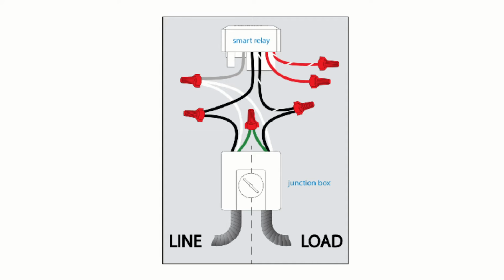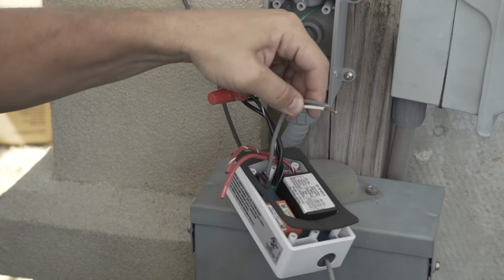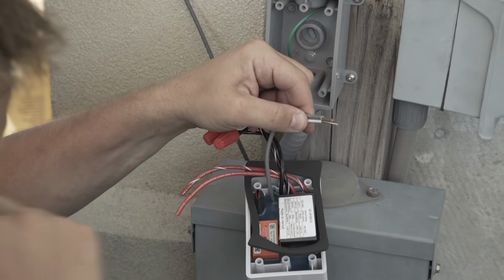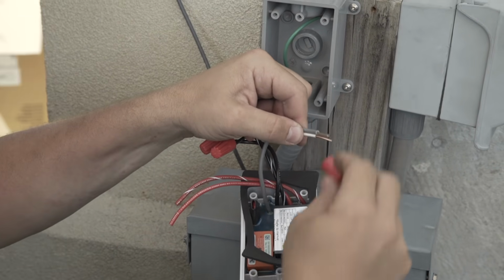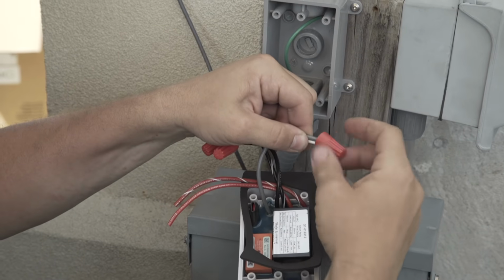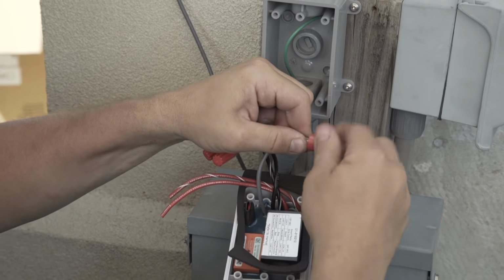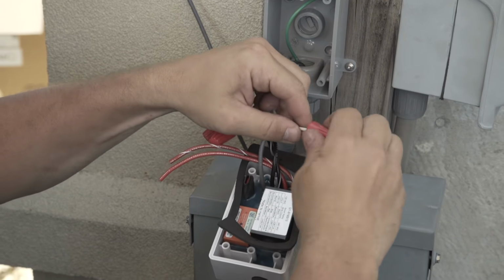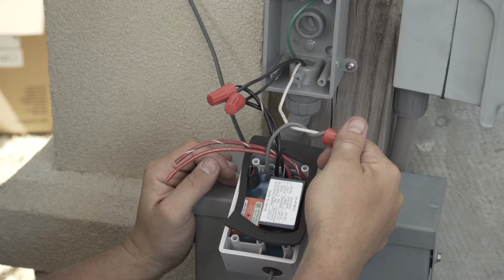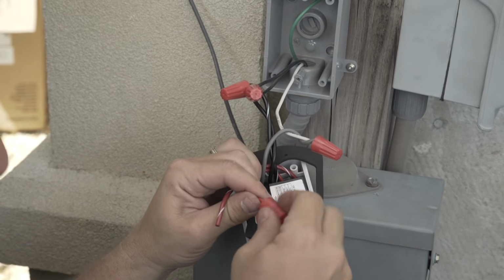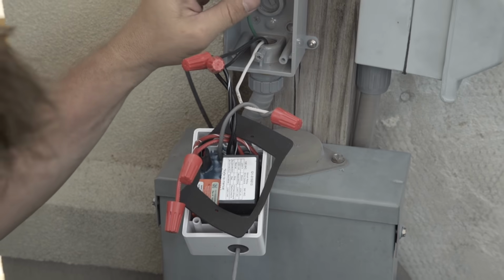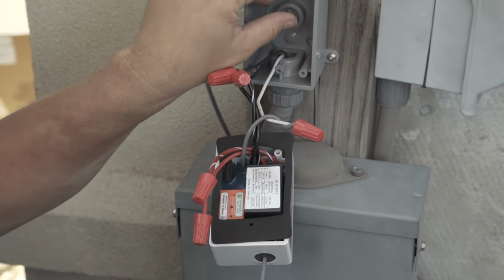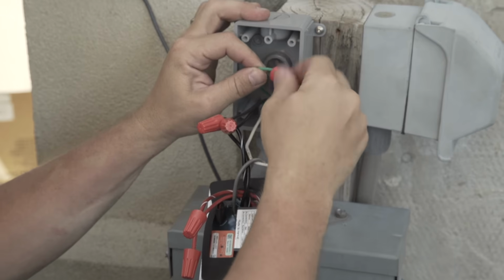It is important that the incoming power line go to the solid black wire off the smart relay and the load be attached to the black and white striped wire. When installing the smart relay in a 115 volt application, a neutral wire will be required. If a neutral wire does not already exist, one will need to be pulled from the power source prior to continuing with the installation. Connect all the neutral wires to the smart relay's gray wire. Make sure the solid red and red and white striped wires are capped individually using the wire nuts supplied. Also connect the 2 ground wires as shown.